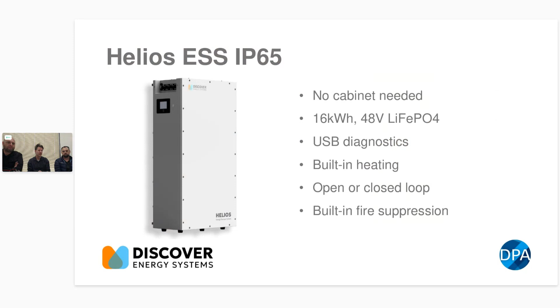So it's the same functional BMS, just much beefier. The other difference is the Helios only has a single pole breaker, so when you install it, you need an additional external 2-pole breaker. With the Rackmount, most of the time you'll have it in a cabinet and be running to a 2-pole breaker anyway. If the batteries are within 2 meters of the inverter, you can use one 2-pole breaker for both the battery and the inverter. It's only if it's greater than 2 meters that you'd need 2 of them serving the same function.